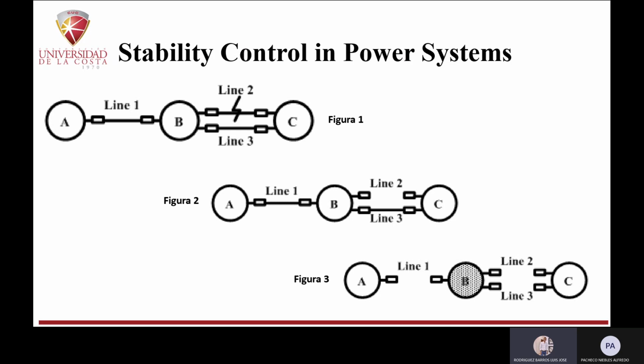Meanwhile, power flow between supplier and consumer is unbalanced in systems A and C. Under stability control devices that measure to solve the problem individually, it can be seen that all relays act correctly in the whole process, but an outage occurs in system B. The possible reason for this cascading event is that the relay and stability control devices only protect their own part and lack the global concept. So the global stability control system is described next.